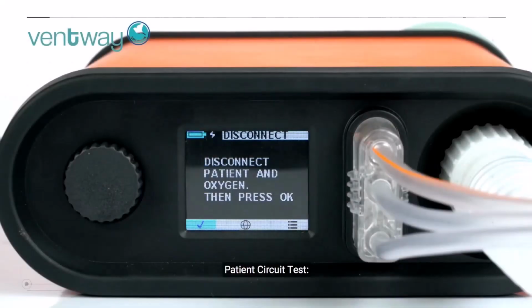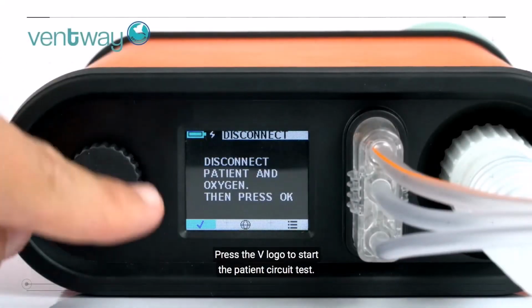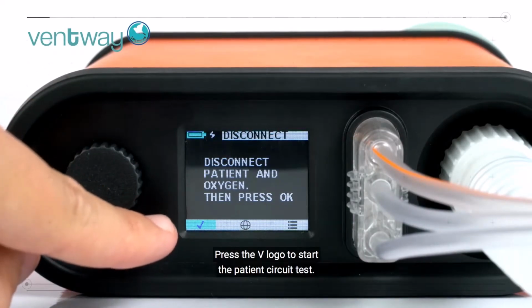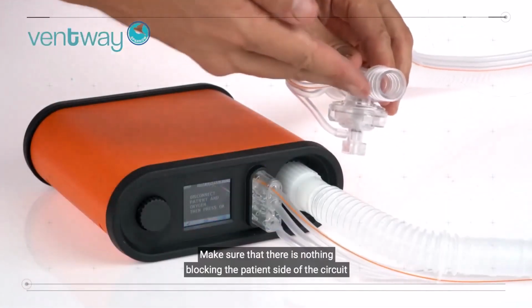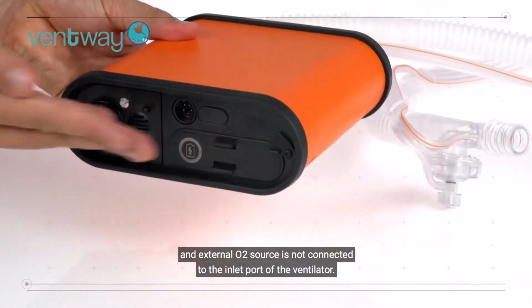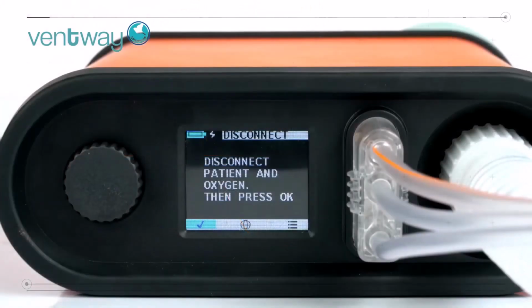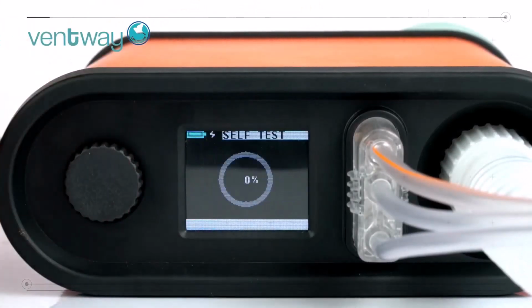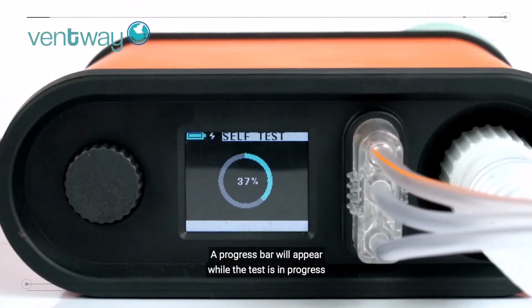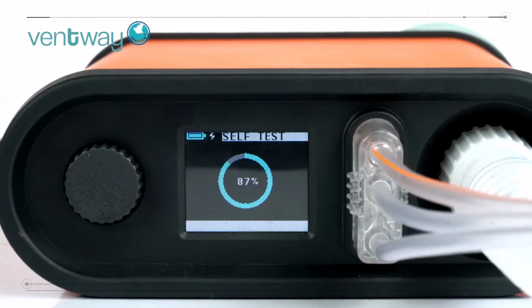Patient circuit test. Press the V logo to start the patient circuit test. Make sure that there is nothing blocking the patient side of the circuit, and the external O2 source is not connected to the inlet port of the ventilator. A progress bar will appear while the test is in progress.